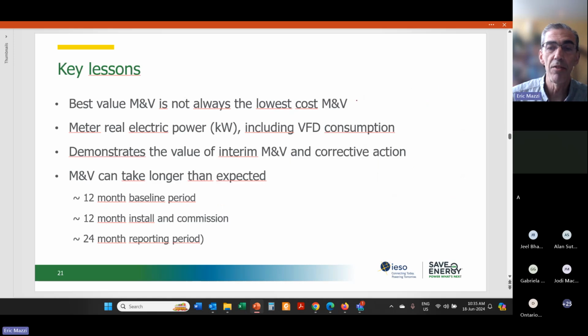Some of the key lessons from this: the best value M&V is not always the lowest cost. This project, even though it's a large building, was very simple in many ways, and arguably the stakeholders could have said there's no need to do M&V here. What could go wrong? You put VFDs in, what could be simpler than that? You program them, they modulate, and you should see your power savings. Why do M&V? Well, M&V was done because of the stakeholder requirements, namely the utility funding contribution.